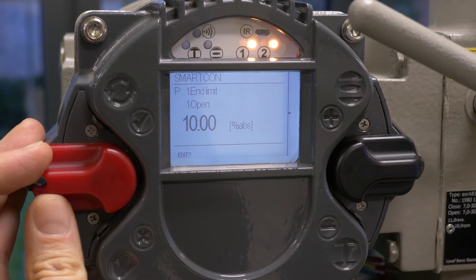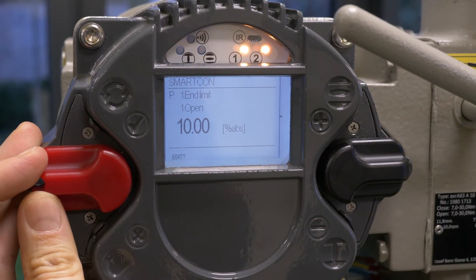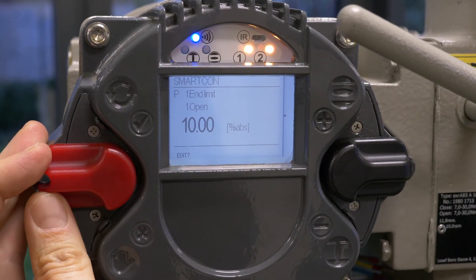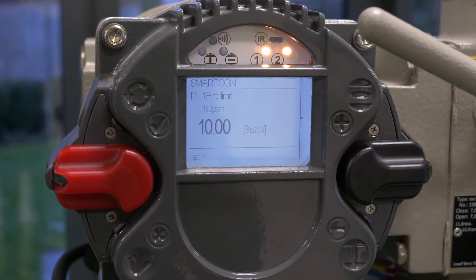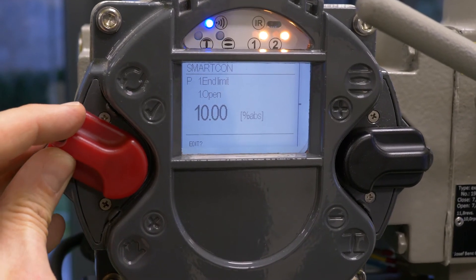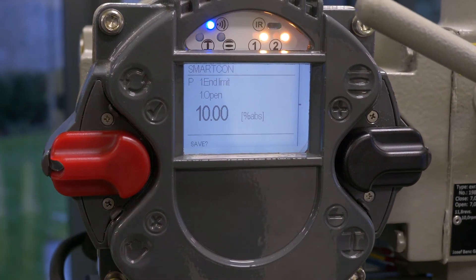For setting the open end limit, use the black selector switch. Move it slowly until you reach parameter P1.1 end limit open. Then use the red selector switch to edit the parameter.